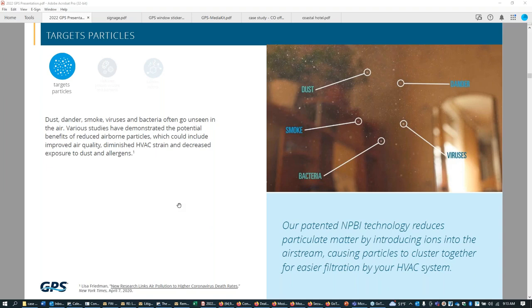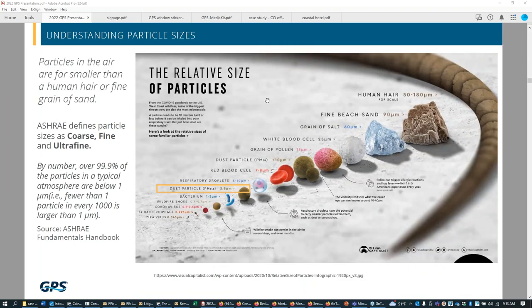whatever filters you have, whether it's MERV 8, MERV 10, MERV 13, the filters are more capable of removing larger particle sizes. This is a chart that just shows relative particle size. You may have heard the metric PM, PM 10, PM 2.5. And what that stands for is the diameter of particulate of a given size. So this chart you may have seen before, but if the human hair is 50 to 180 micrometers in diameter, you get smaller with salt, pollen, dust, and PM 2.5 is a common industry and EPA metric to talk about airborne particulate.